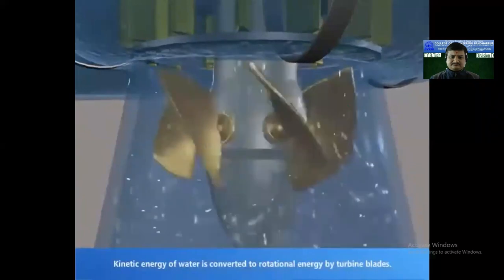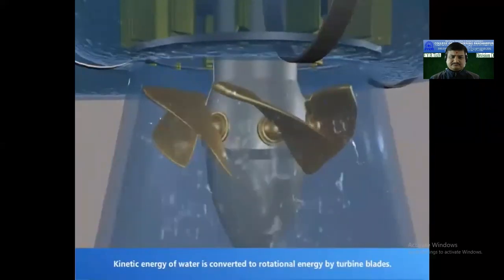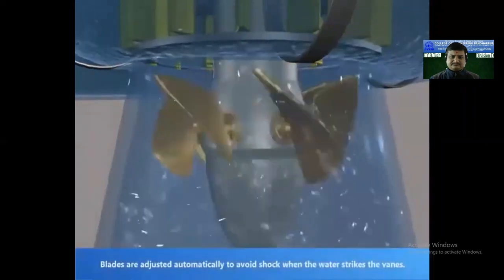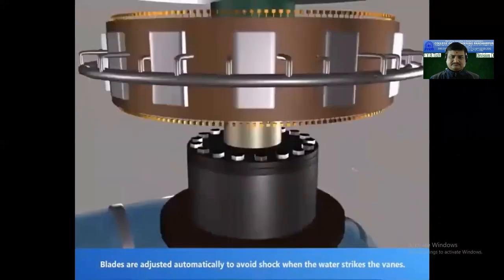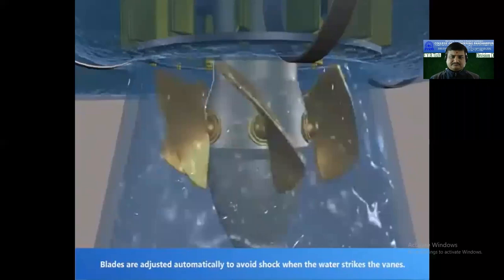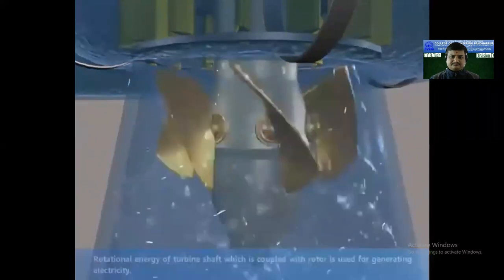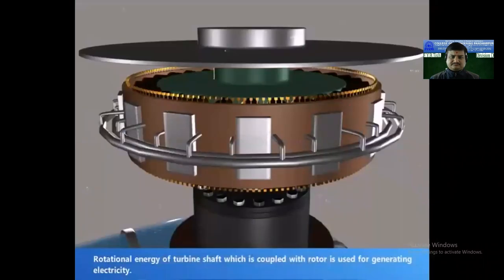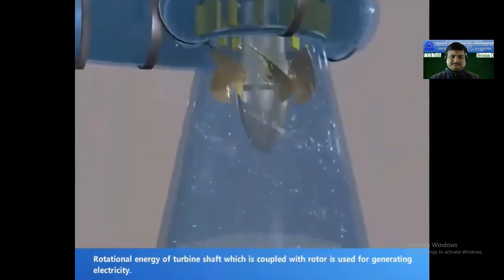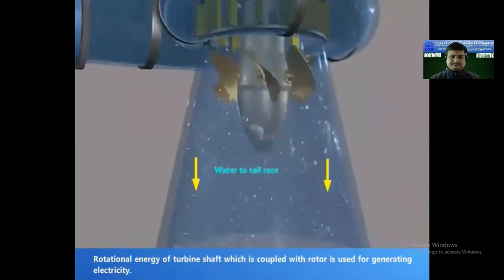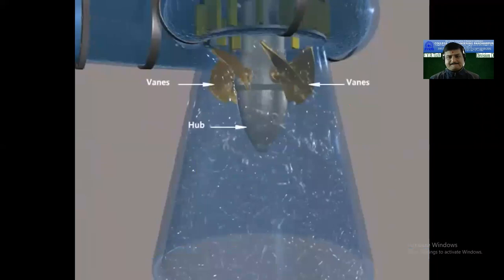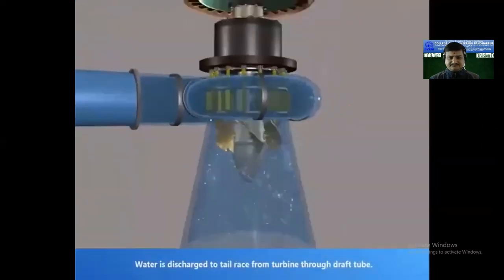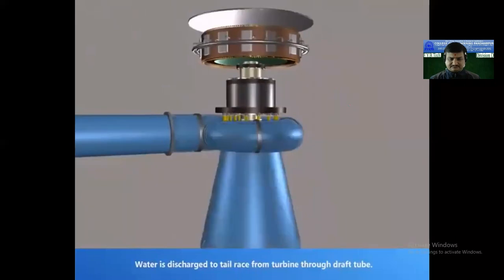Kinetic energy of water is converted to rotational energy by turbine blades. Blades are adjusted automatically to avoid shock when the water strikes the vanes. Rotational energy of the turbine shaft, which is coupled with the rotor, is used for generating electricity. Hub, vanes. Water is discharged to the tail race from the turbine through the draft tube.